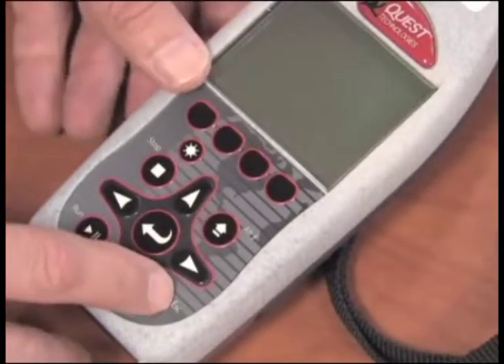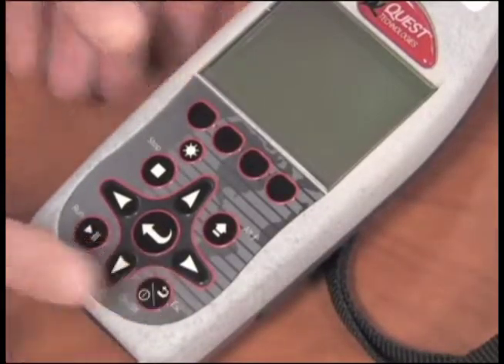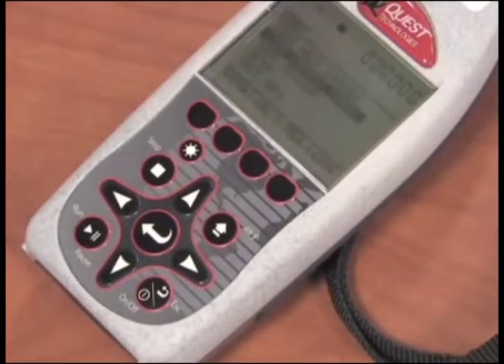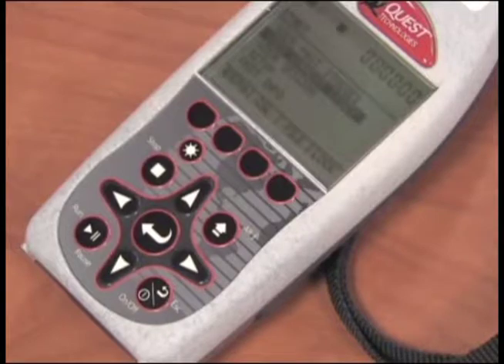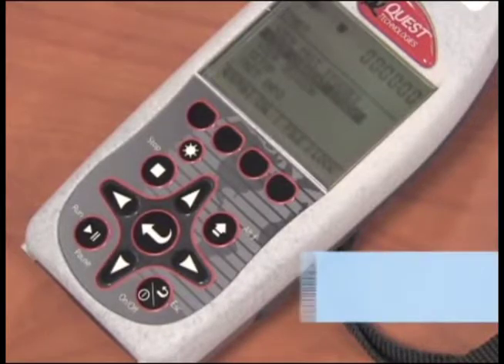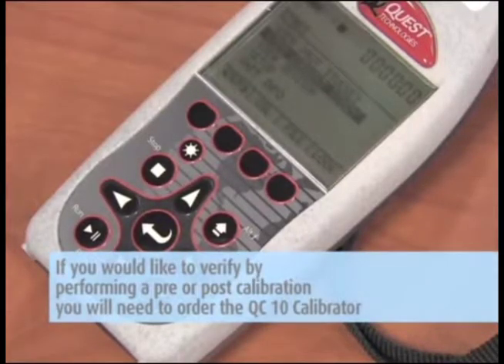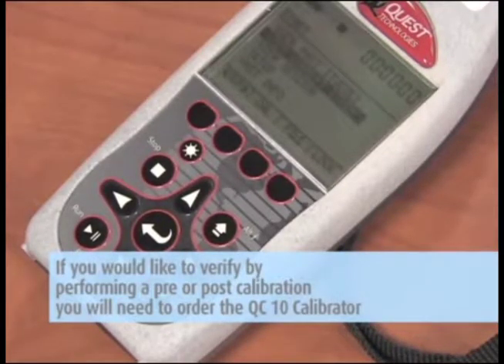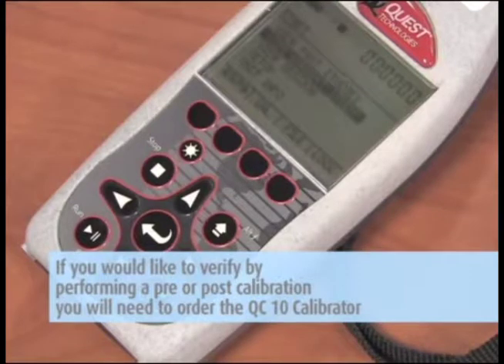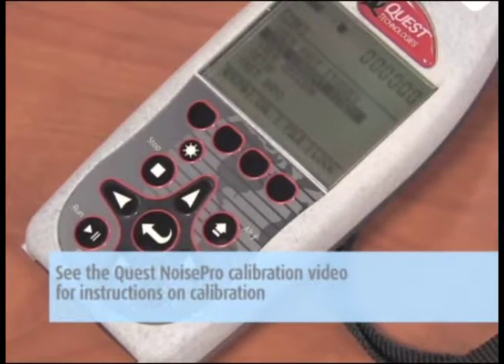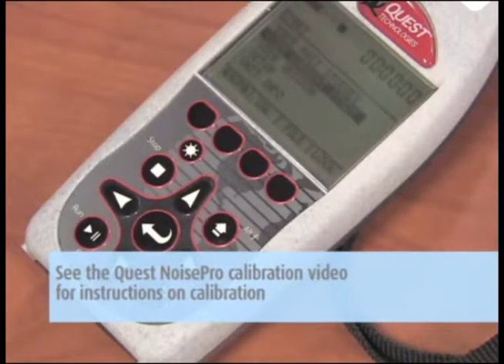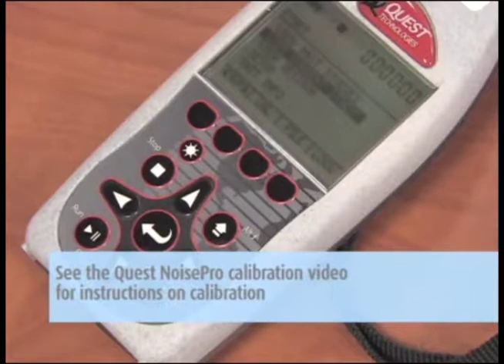Press the on button and turn the unit on. The unit has been preset and pre-calibrated. If you would like to verify by performing a pre and/or post calibration, you will need to order the QC10 calibrator. See the Quest NoisePro Calibration video for instructions on calibration.